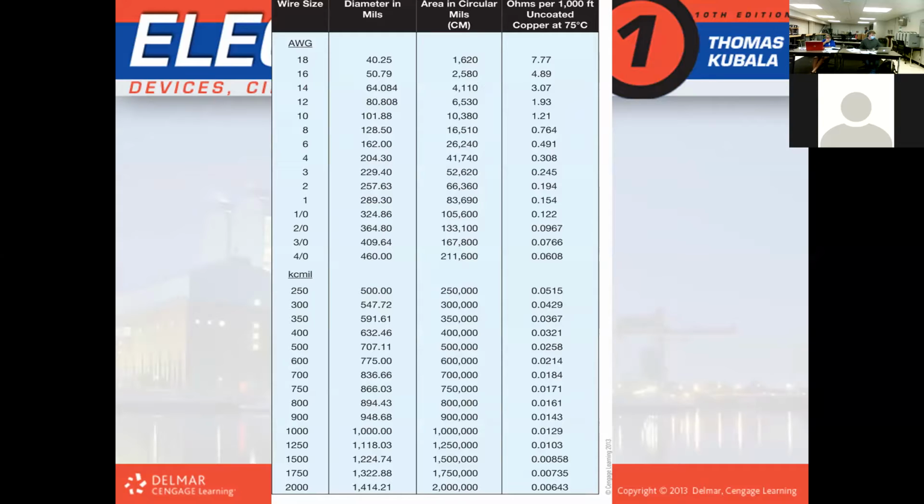Now, the question says you have a 1 foot piece of copper wire, 167 degrees Fahrenheit, which is also 75 degrees Celsius. 75 degrees C is what it says in the book, but that equals 167 Fahrenheit. It has a resistance of 0.00777 ohms for 1 foot. Now the column on the right on the table gives resistance for how many feet? 1,000 foot. So you got to figure out from your question, that's 1 foot. So what would 1,000 foot of that be in resistance?